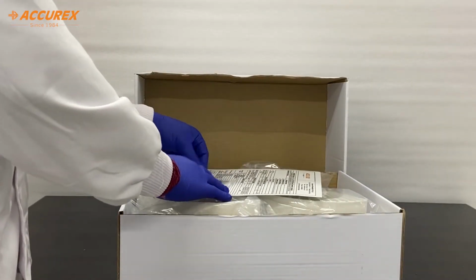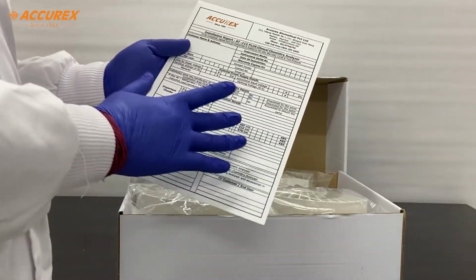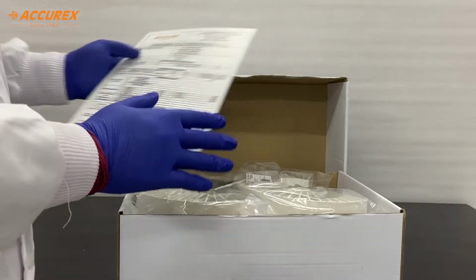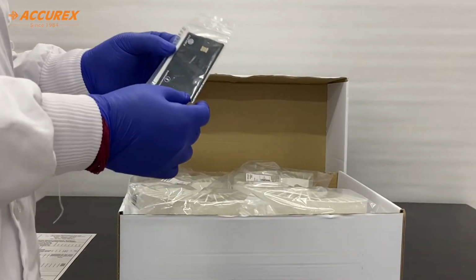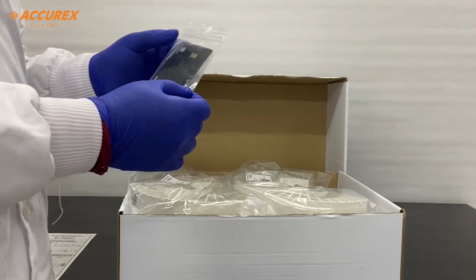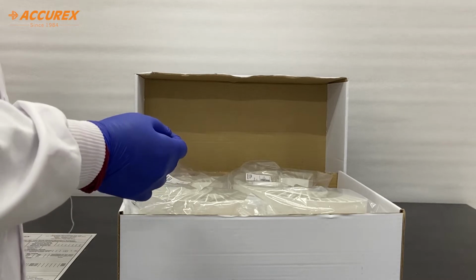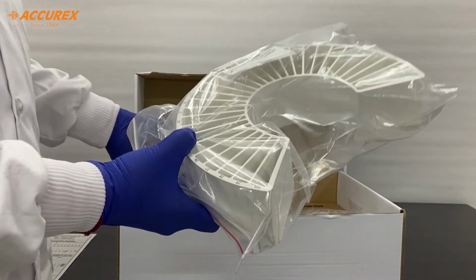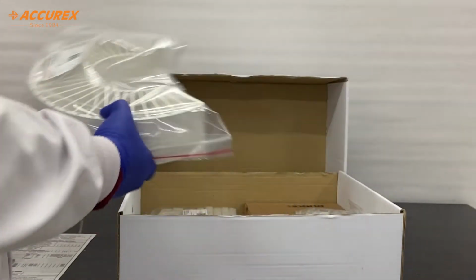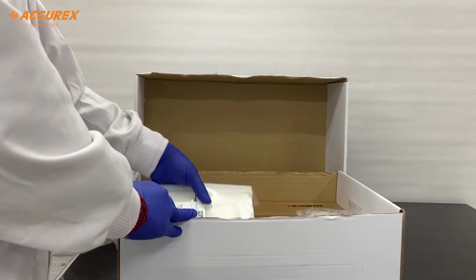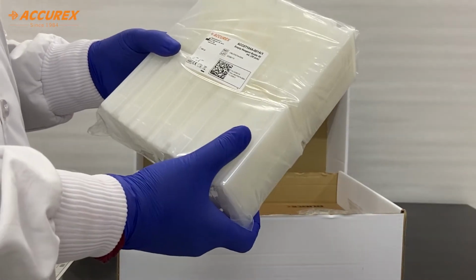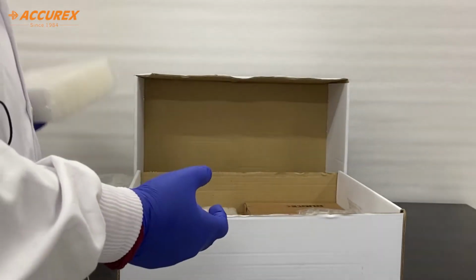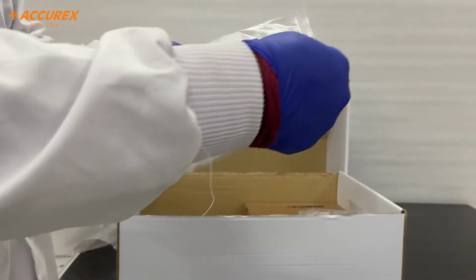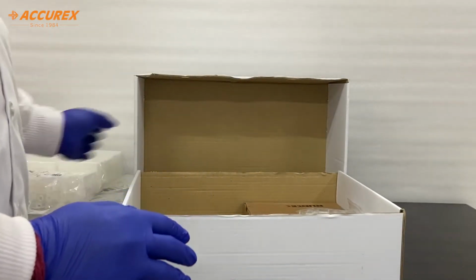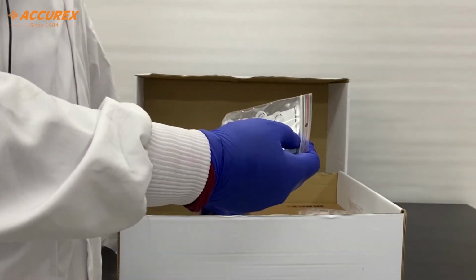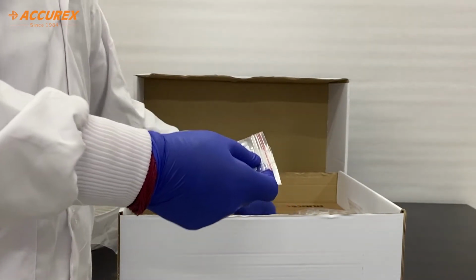First, you can see there is an installation report. This report is filled in by the engineer during installation. Then we have a card. This card has software, and the engineer uses it for installation purposes. Then there are two sets of reagent bottle trays. Then you can find empty reagent bottles of 50 ml, 30 pieces. In the same way, we have 20 ml bottles, 30 pieces. Then we have caps for these bottles. There are three sets of caps which can be used.